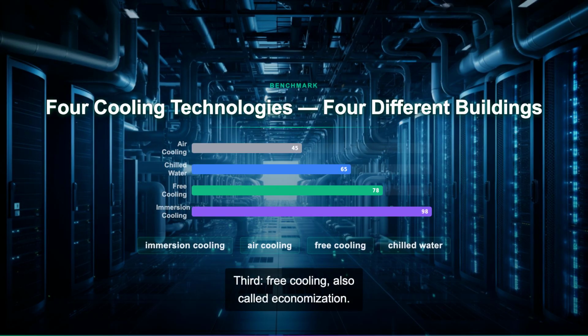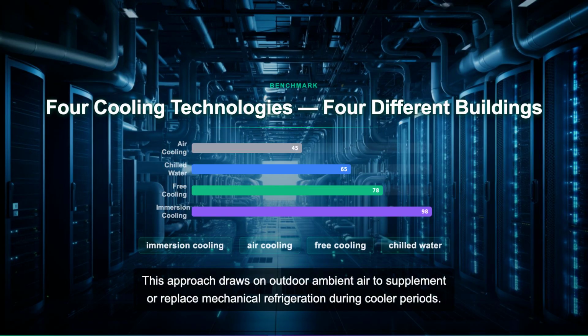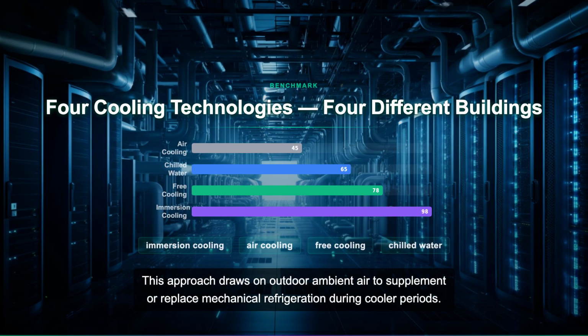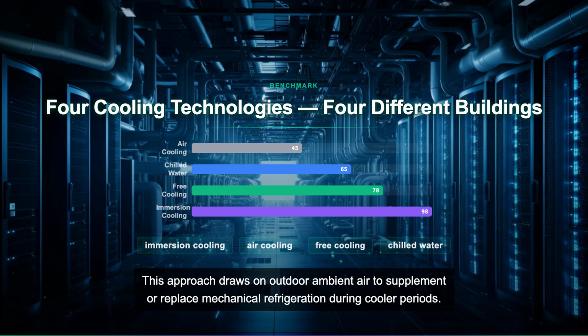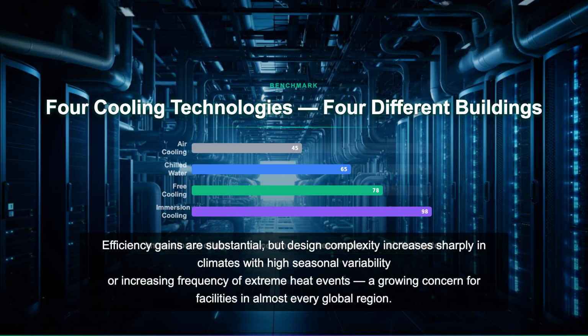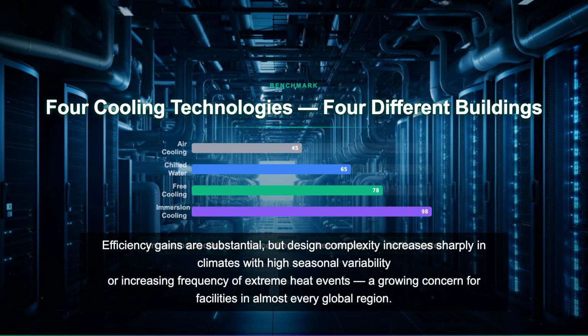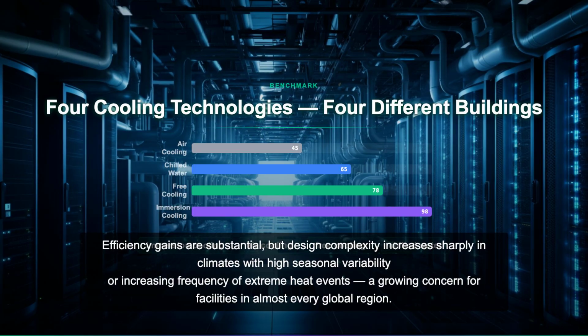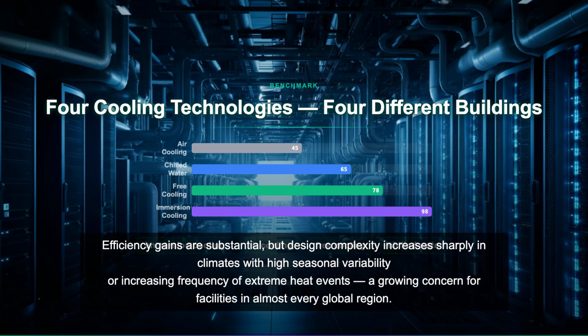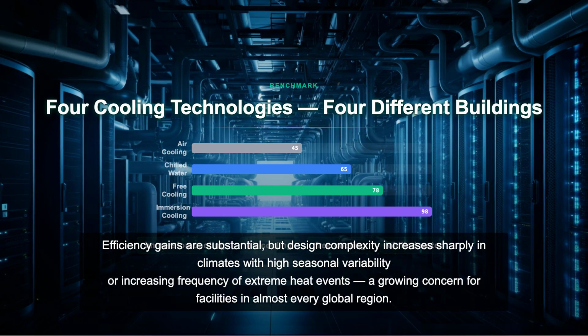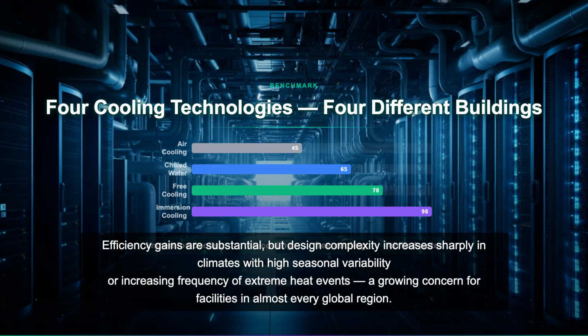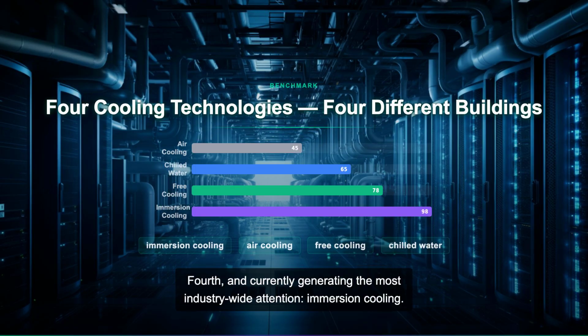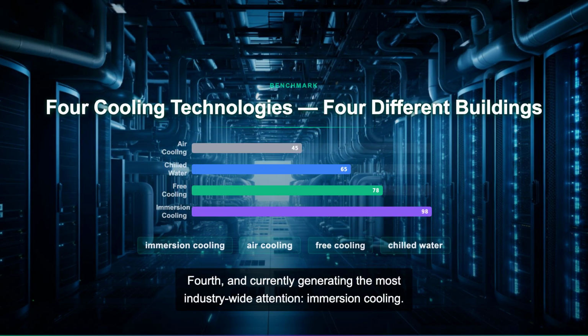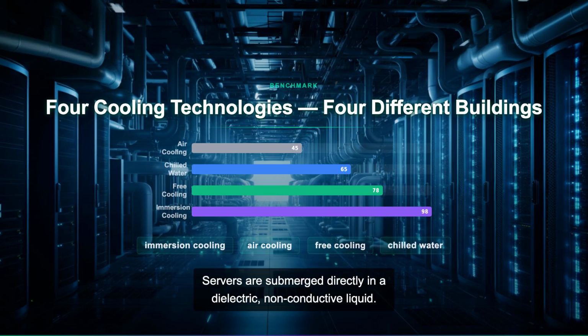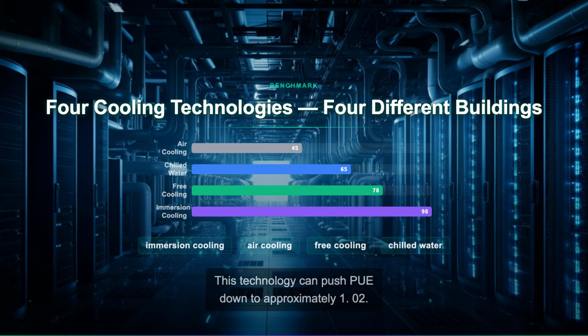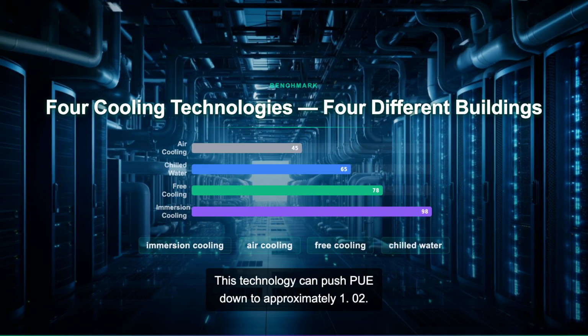Third, free cooling, also called economization. This approach draws on outdoor ambient air to supplement or replace mechanical refrigeration during cooler periods. Efficiency gains are substantial, but design complexity increases sharply in climates with high seasonal variability or increasing frequency of extreme heat events, a growing concern for facilities in almost every global region. Fourth, and currently generating the most industry-wide attention, immersion cooling. Servers are submerged directly in a dielectric, non-conductive liquid. This technology can push PUE down to approximately 1.02.